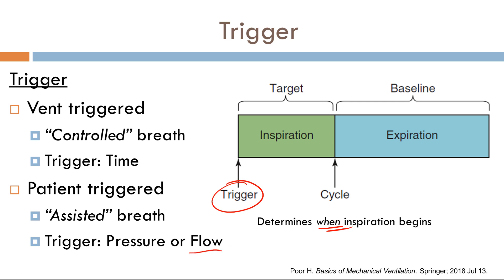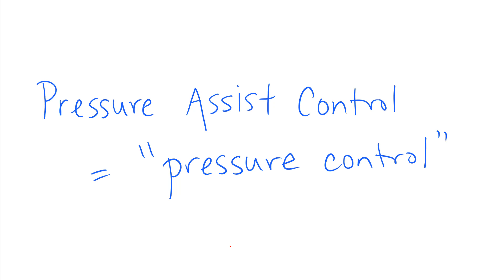For controlled breaths, the time between each delivered breath is determined by the respiratory rate. For assisted breaths, you have to plug in a numerical value for pressure or flow. For example, if the flow threshold is set to three liters per minute, that means if the patient initiates a breath and it surpasses the threshold of three liters per minute, then that breath is delivered.